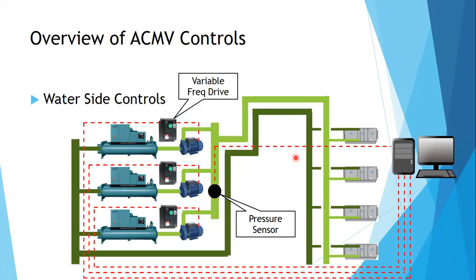Another way of doing it is with VSD again. This pressure sensor, same logic, will sense an increase or decrease in pressure when this air handling unit is turned off. When this air handling unit is turned off, this pressure sensor will sense, oh, too much pressure, and will send a signal to the BMS or to the PLC. The PLC will then send a signal to your VSD telling the pump, hey, lower down your speed. We have too much pressure already. This will ensure that there's enough flow to all the air handling units while only giving the appropriate amount of flow, not too much. Okay.